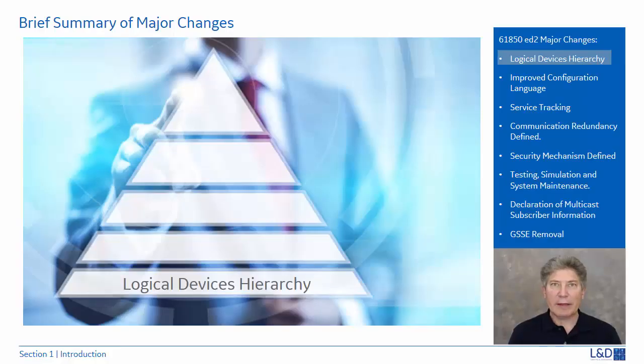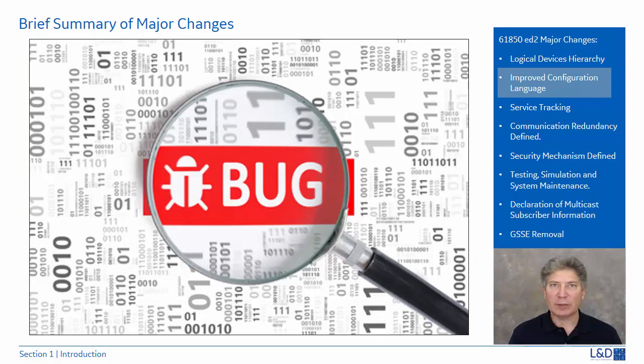Here's a brief summary of some of the major changes that were incorporated into IEC 61850 Edition 2. A distinct logical devices hierarchy, where the logical nodes have been grouped into specific logical device headings. Improvements in the substation configuration language tool. In addition, the standard removes some of the ambiguity that was associated with file creation, which allows for a more robust tool to generate mapping of 61850 signals across multiple vendors' products.